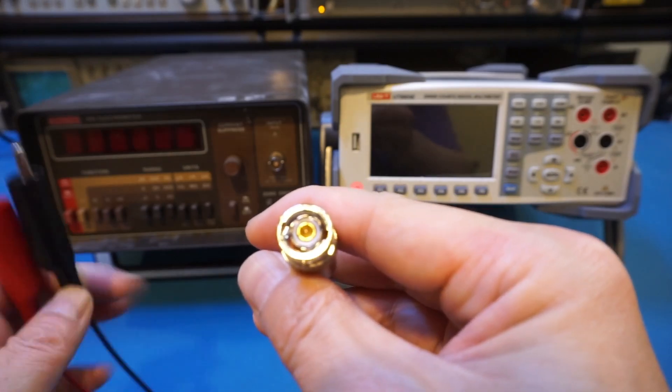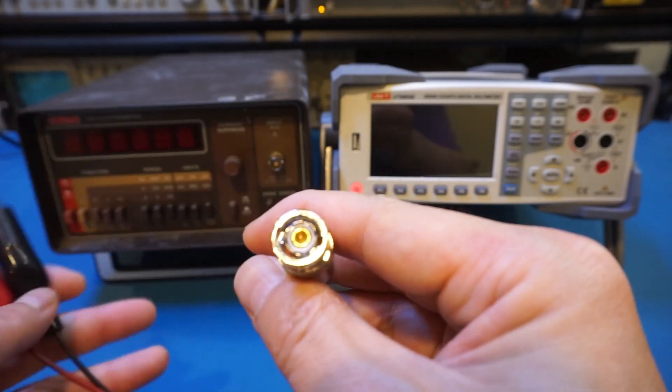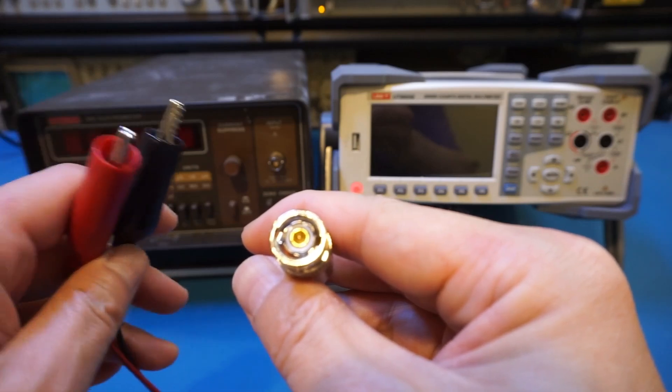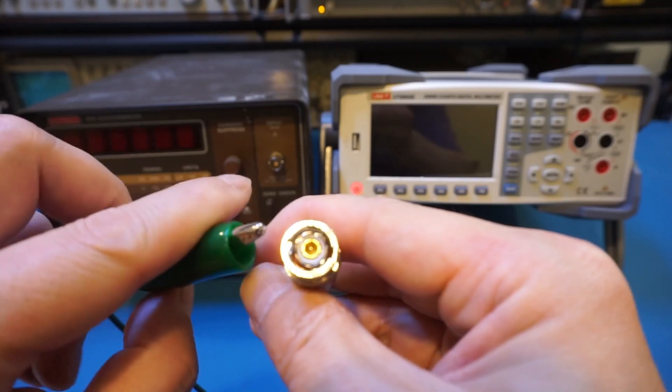Besides your typical black and red leads you find in a BNC to banana plug cable, you also get this green connector, and that is connected to the inner shielding, which is the guard terminal.